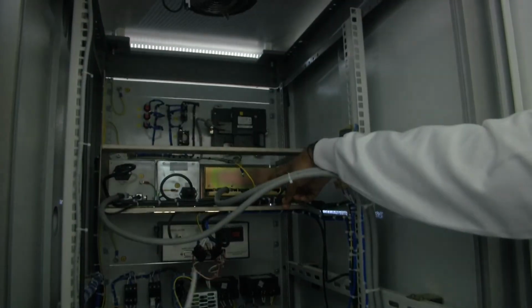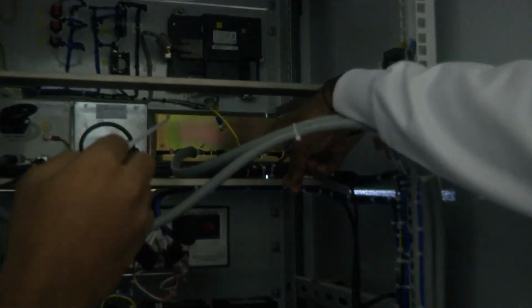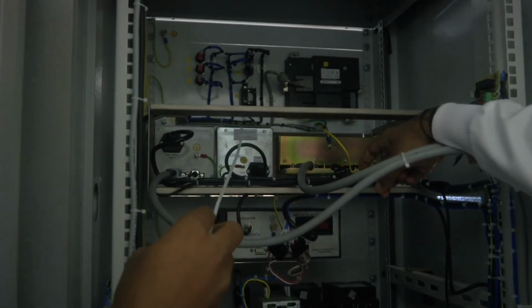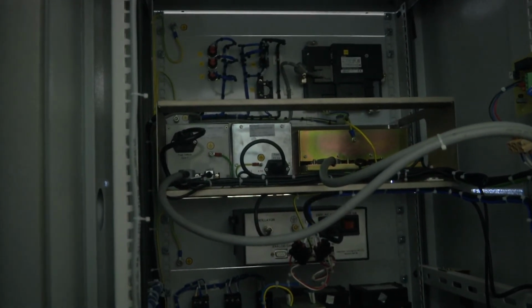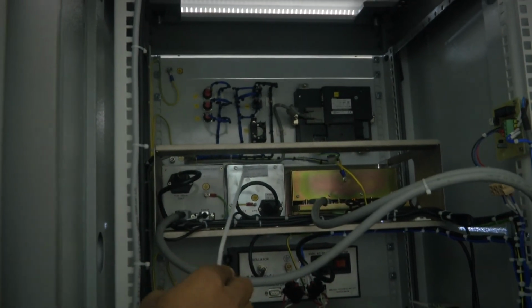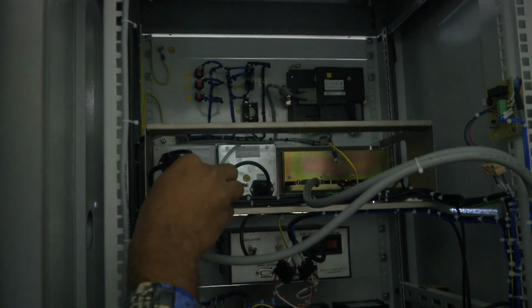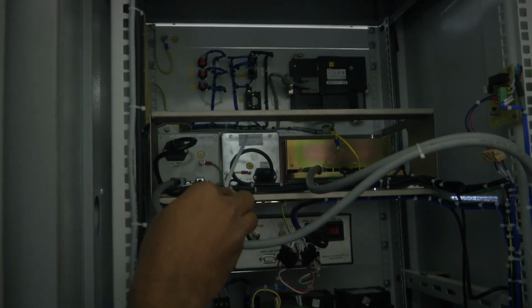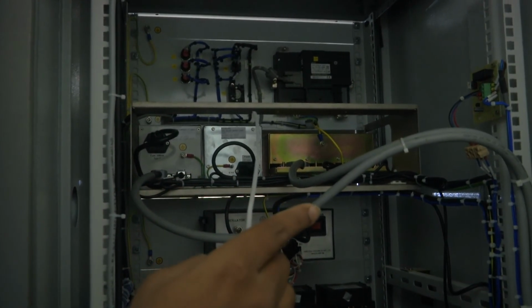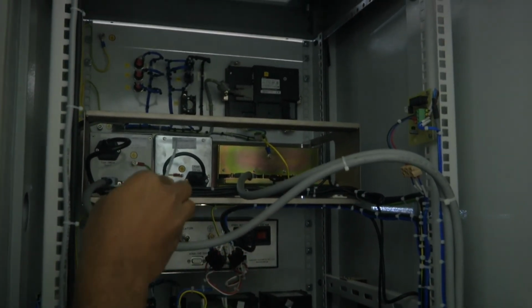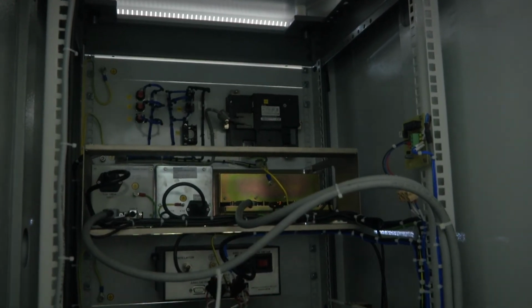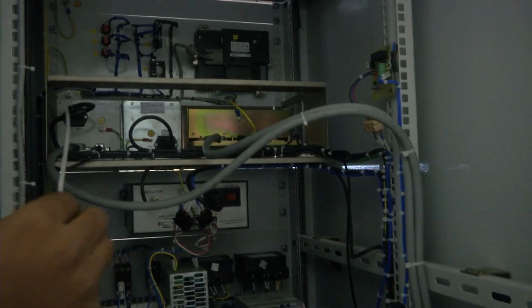What is this one actually? It is to operate the EB source. We have given 3 types. One is the EB motorized turret, to select the source position. In the EB gun, 4 source selection pockets are there. To operate that motorized turret, this drive is there. Then the EB beam sweep controller unit. In the EB gun we get X and Y axes, so to get that waveform, whether X or Y, we go through this beam sweep unit to set the axis and control the waveforms of the electron beam. And for turret movement, you have the first one, the motorized turret movement. That is one control unit there.